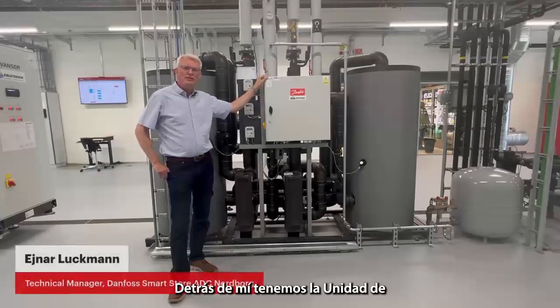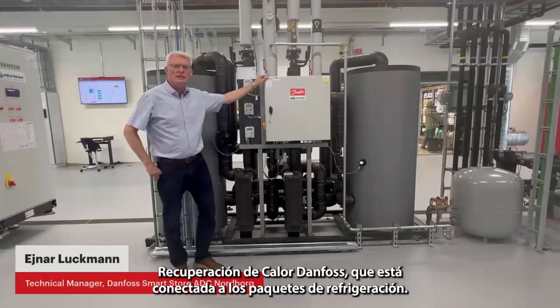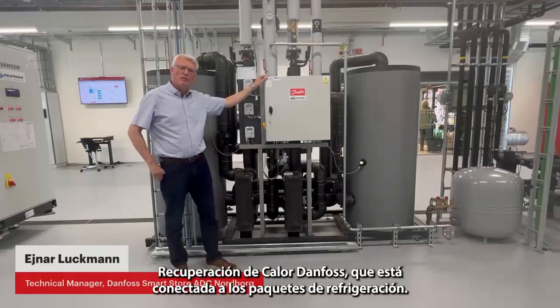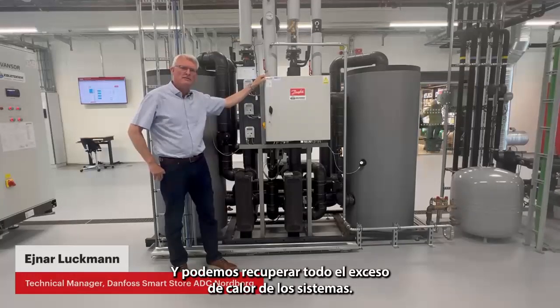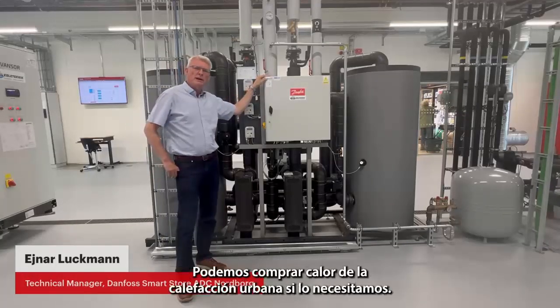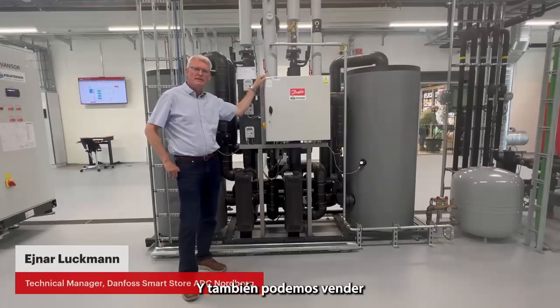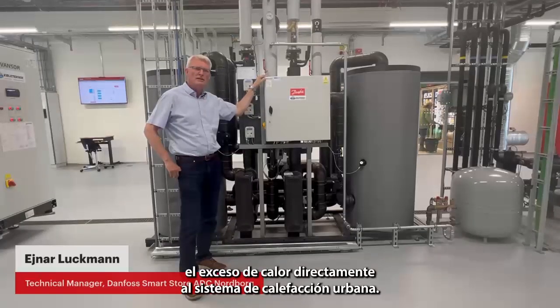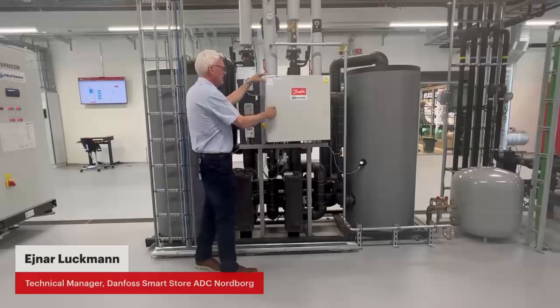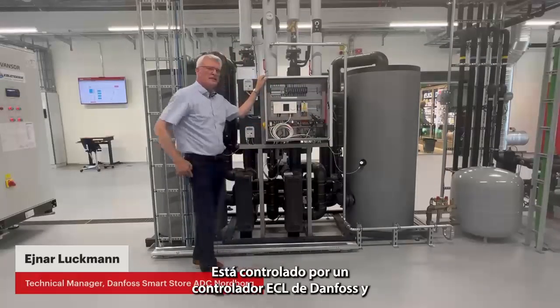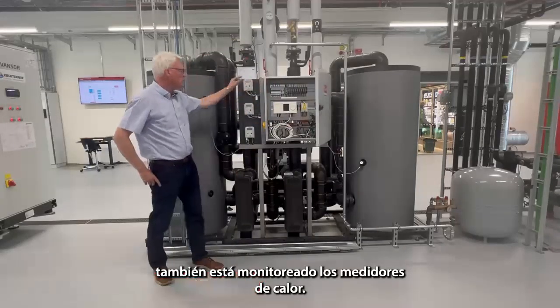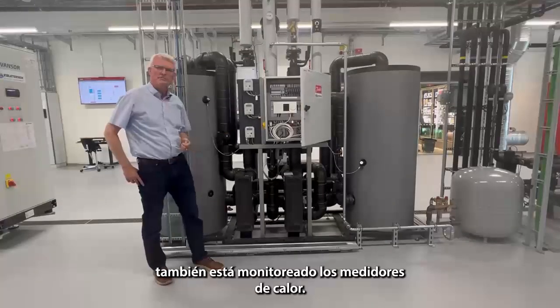Behind me we have the Danfoss heat recovery unit, which is connected to the refrigeration packs, and we can recover all the excess heat from the systems. We can buy heat from the district heating if we need, and we can also sell back excess heat directly to the district heating system. It's controlled by a Danfoss ECL controller, and also monitored by Danfoss heat meters.